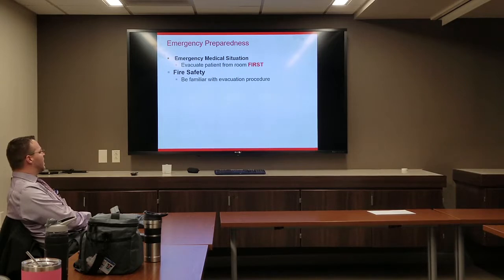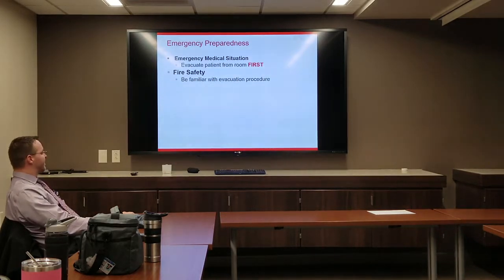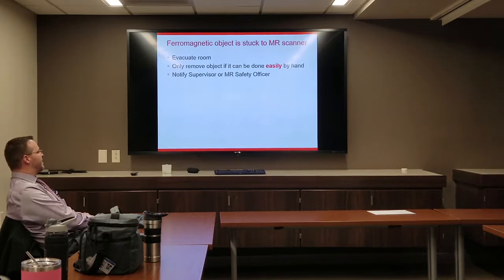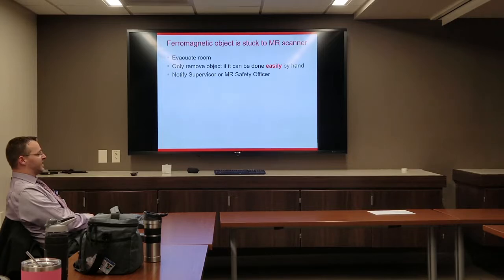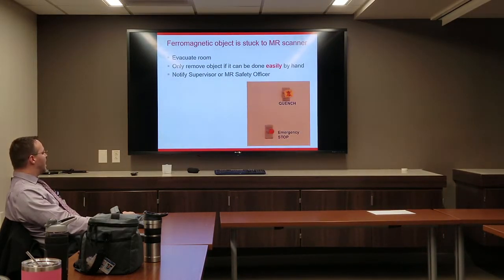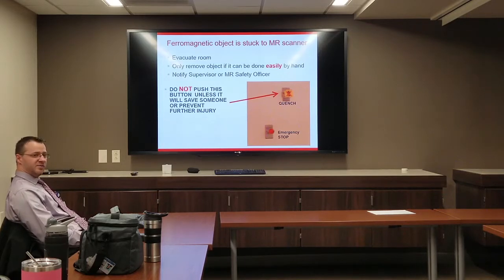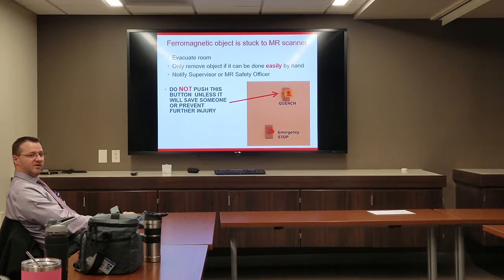For emergency preparedness: in any emergency medical situation, evacuate the patient from the room first. At OSU, we evacuate before even calling a code, because the last thing you want is a code team running into the MR room causing additional safety injuries. With fire safety, be familiar with your fire evacuation procedures. If a ferromagnetic object is found stuck to the MR scanner, first evacuate the room, then only remove the object if it can be done easily by hand, and notify your supervisor or MR safety officer. Do not push the quench button unless it's going to save someone's life or prevent further injury — a quench can cause magnet damage and tens of thousands of dollars in cryogen replacement costs and lost revenue.